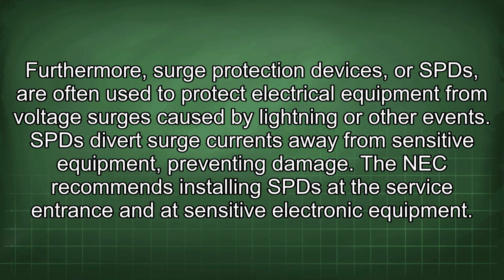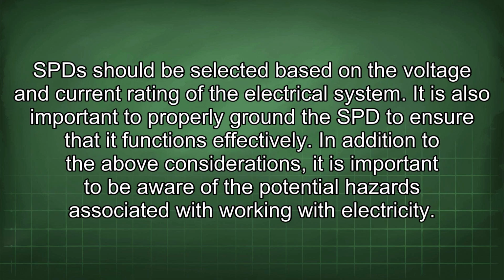Furthermore, surge protection devices, or SPDs, are often used to protect electrical equipment from voltage surges caused by lightning or other events. SPDs divert surge currents away from sensitive equipment, preventing damage. The NEC recommends installing SPDs at the service entrance and at sensitive electronic equipment. SPDs should be selected based on the voltage and current rating of the electrical system. It is also important to properly ground the SPD to ensure that it functions effectively.